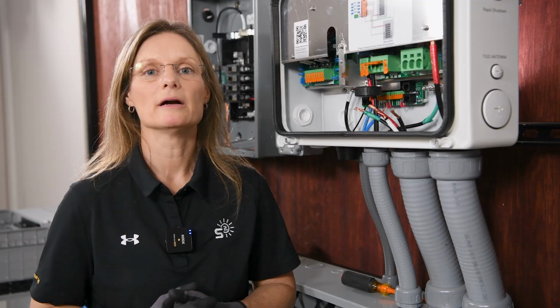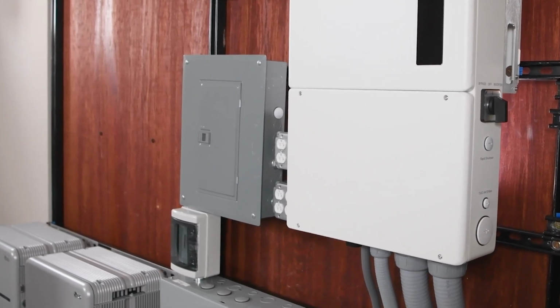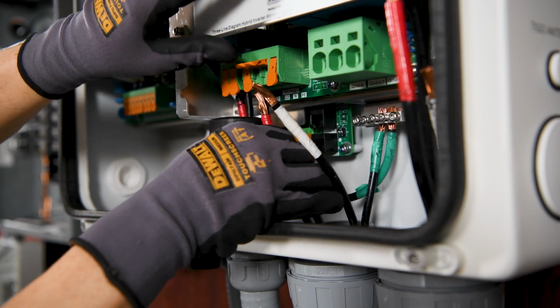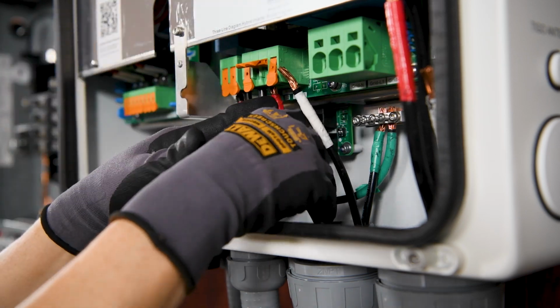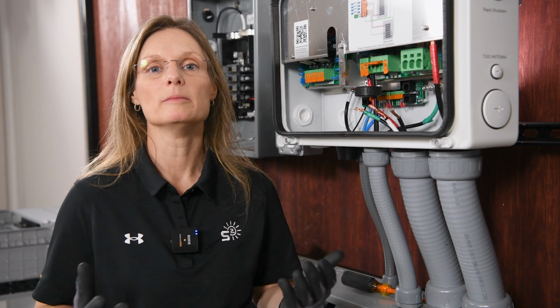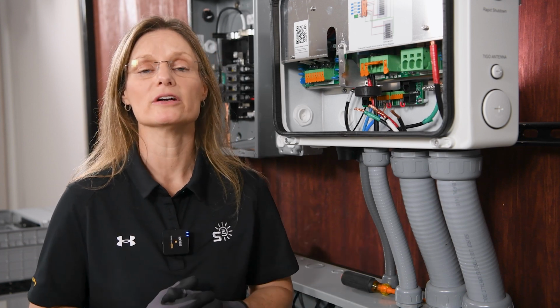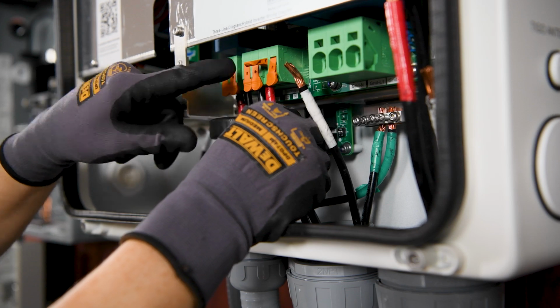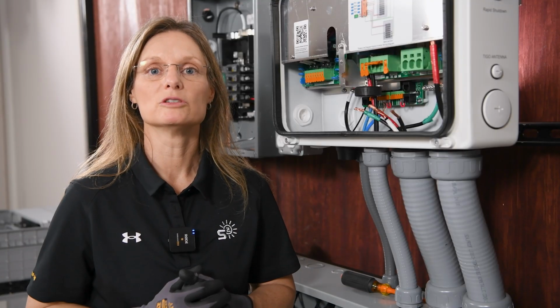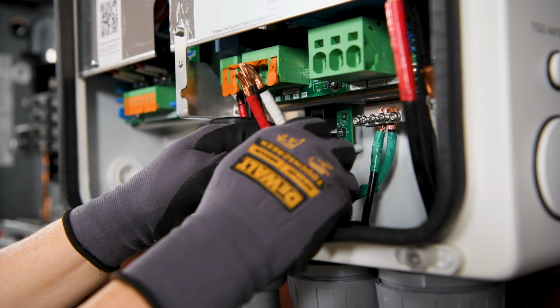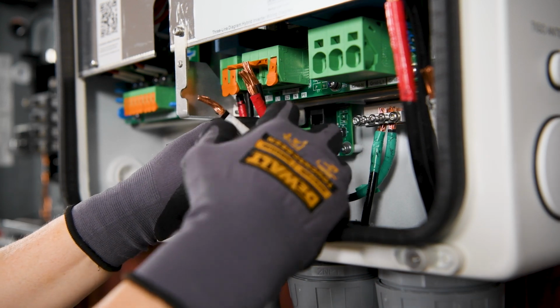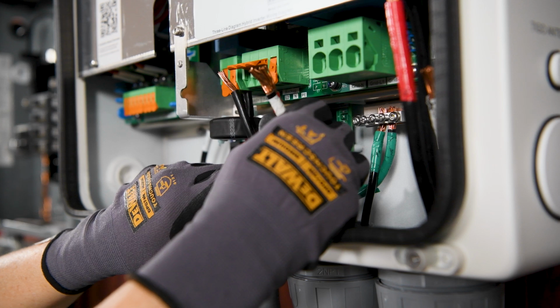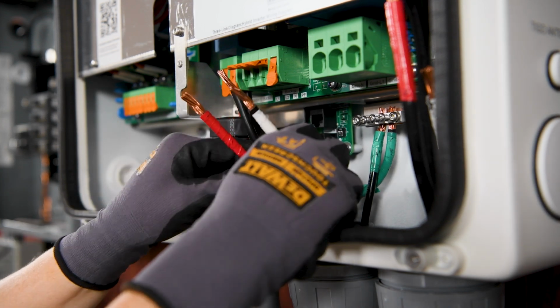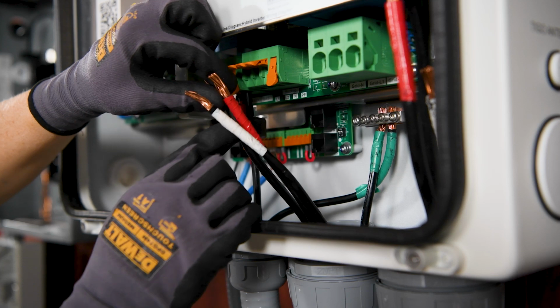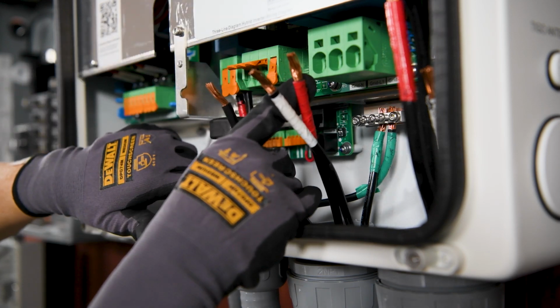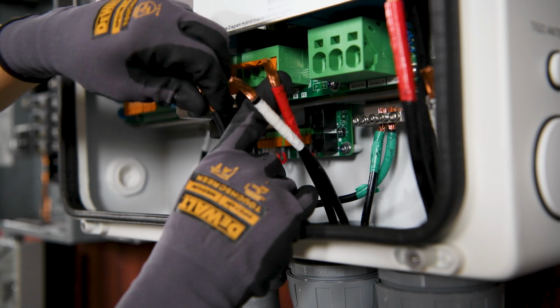Now we'll wire up our backup panel or our critical loads panel. We're using a 6-gauge wire due to the fact that our inverter can handle 47.5 amps, and the 120% rule means that we will run this through a 60 amp breaker in our backup loads panel. We'll run our line 1, line 2, and neutral to our backup loads panel, and we'll show you how to do that. So with the AC side of things, it's important to note that L1 is typically black, L2 is typically red, and neutral is white. So it's a little bit different for battery being positive red and black being negative.